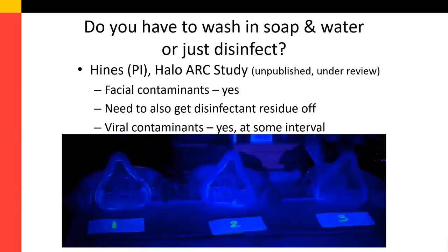And then after the masks were cleaned and disinfected or just disinfected, we looked at the masks again to see if all the fluorescent particle was removed. What we saw was that on the mask that had only been wiped with disinfectant, the fluorescent lotion was not completely removed. So from a facial contaminant standpoint, we do think you need to include a step that includes cleaning with soap and water.